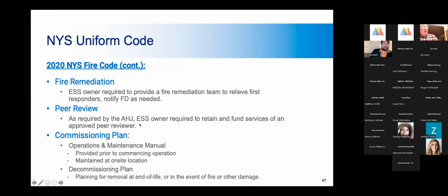Peer review. Hearing me talk so much about how the 9540A test is a packet of results for your interpretation, I could understand if that sounds intimidating. I've been doing this type of work since before 2016, before there was a UL 9540A test, and I don't know 100% of what they're saying when I see them. That's where the peer review requirement kicks in: you, as the authority having jurisdiction, have the authority to require the energy storage developer to pay for a third-party engineer, typically, or expert otherwise approved by the AHJ, to review those plans, the 9540A report, and everything associated with this project, to make sure everything is up to code and safe.